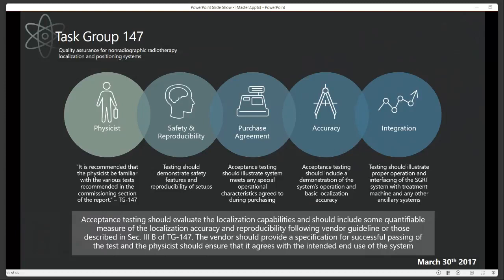The physicist should be aware of Task Group 147 prior to doing any type of acceptance testing, because you need to know what the tests are before you buy something so that you can make sure that it's going to meet those specifications. The acceptance testing should demonstrate to the physicist safety and reproducibility. Nobody wants a system that won't put something in the same spot twice. If there's any special purchasing agreement, if you've bought something with special hardware like a patient couch or remotes or something like that through the various vendors, you should ensure that the hardware that you've purchased does interact with the software correctly and does do what you agreed to in the purchase agreement.